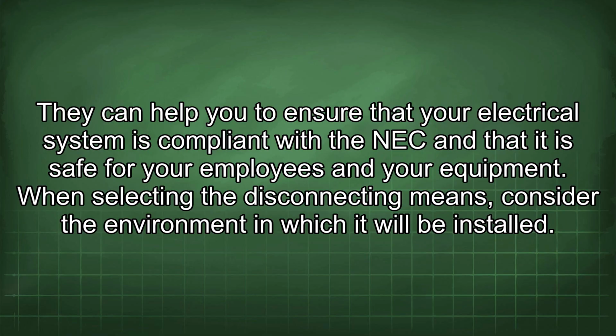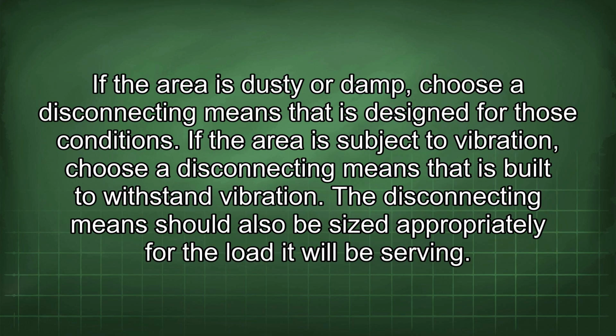When selecting the disconnecting means, consider the environment in which it will be installed. If the area is dusty or damp, choose a disconnecting means that is designed for those conditions. If the area is subject to vibration, choose a disconnecting means that is built to withstand vibration. The disconnecting means should also be sized appropriately for the load it will be serving.